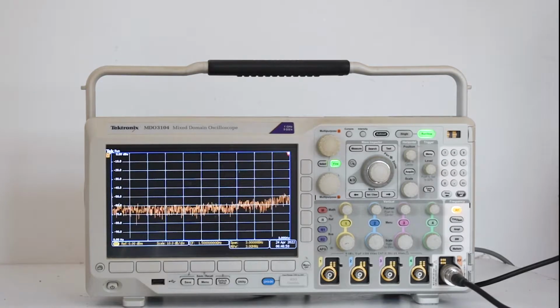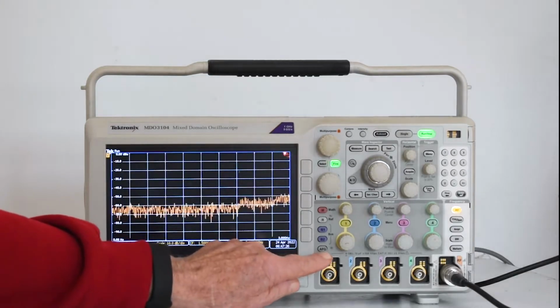To demonstrate the RF channel in this instrument, I have run a BNC cable from the AFG port on the rear panel to the RF port on the front panel. The BNC cable connection to the RF input port requires an RF adapter, which Tektronix furnishes with the instrument. We'll use the internal arbitrary function generator to supply a sine wave to the RF input.